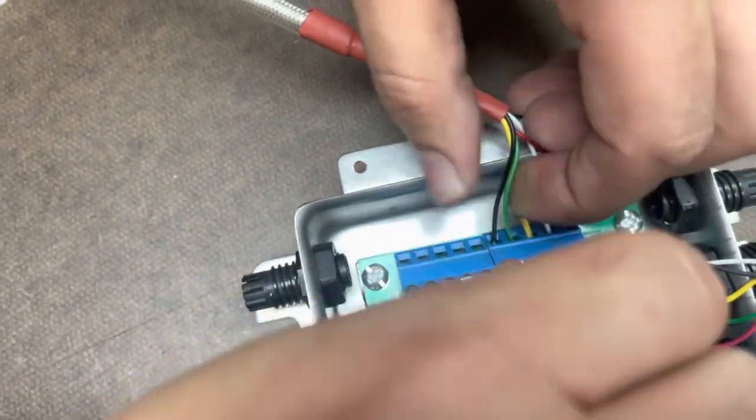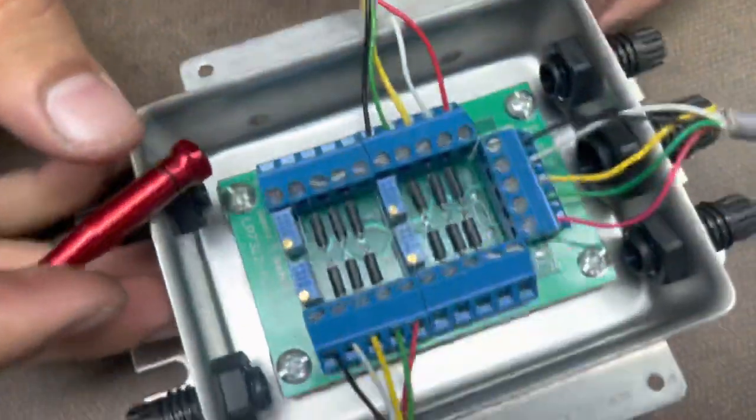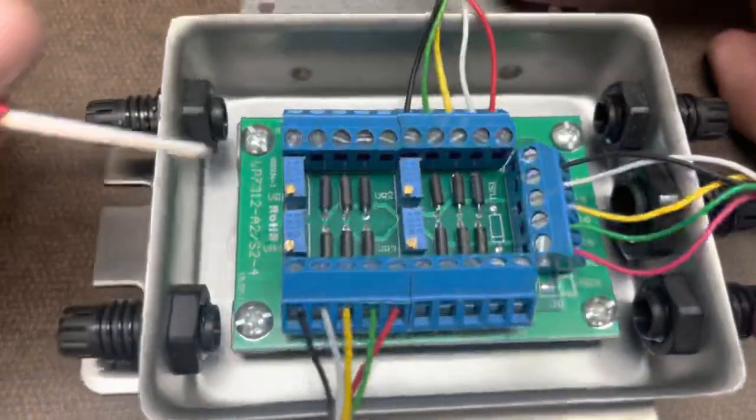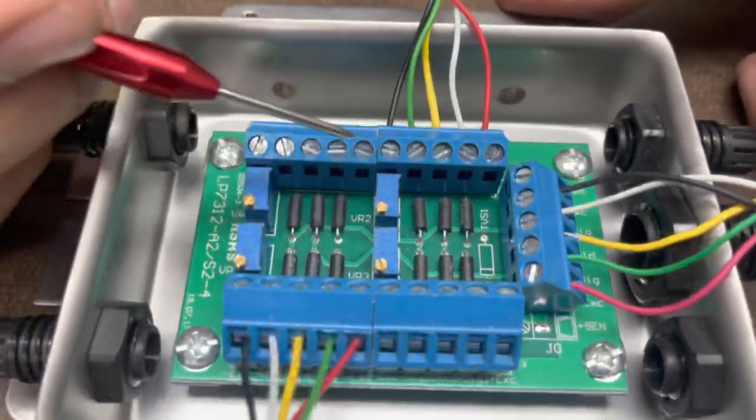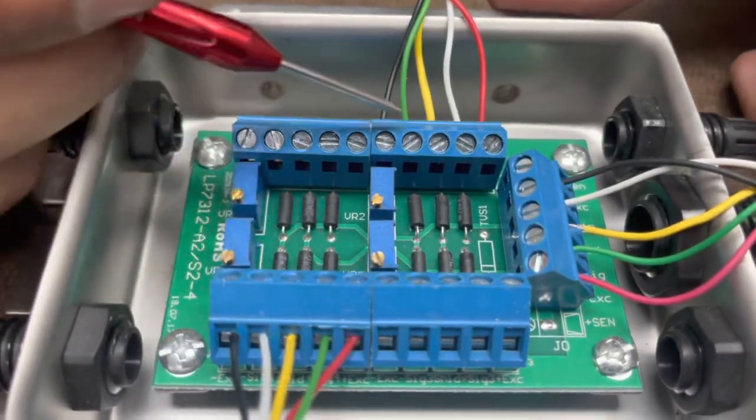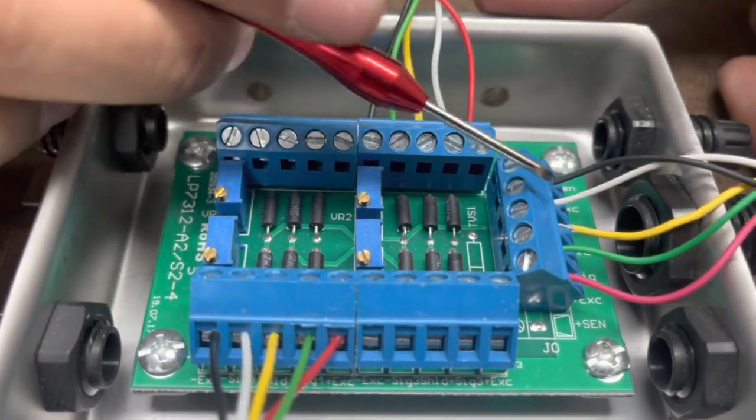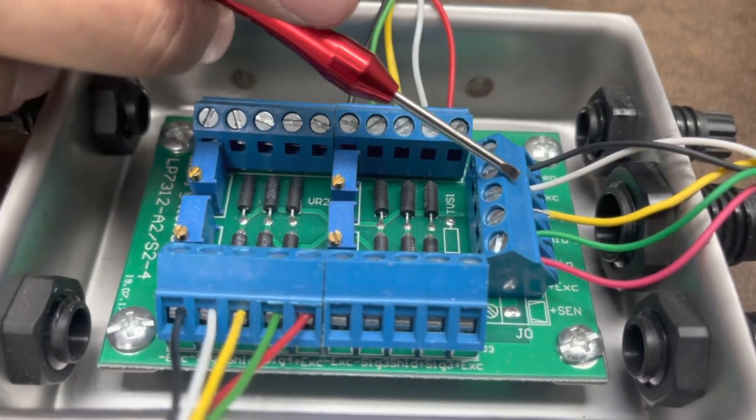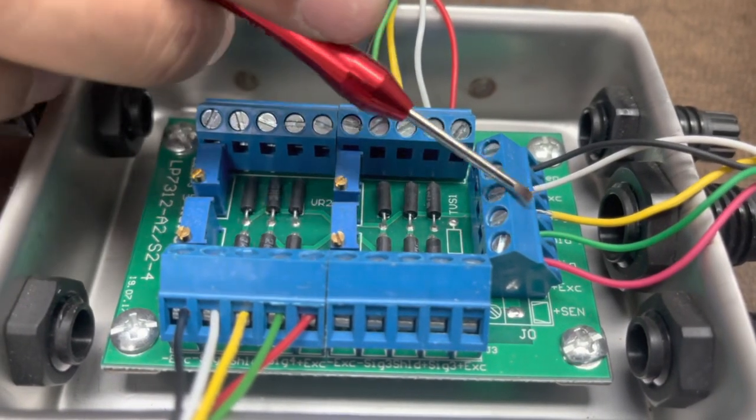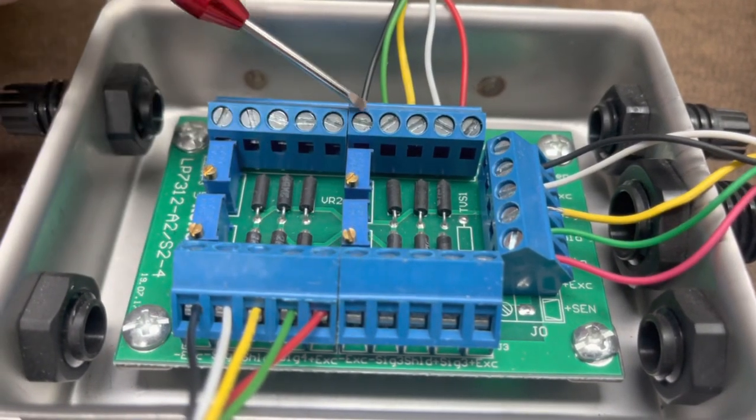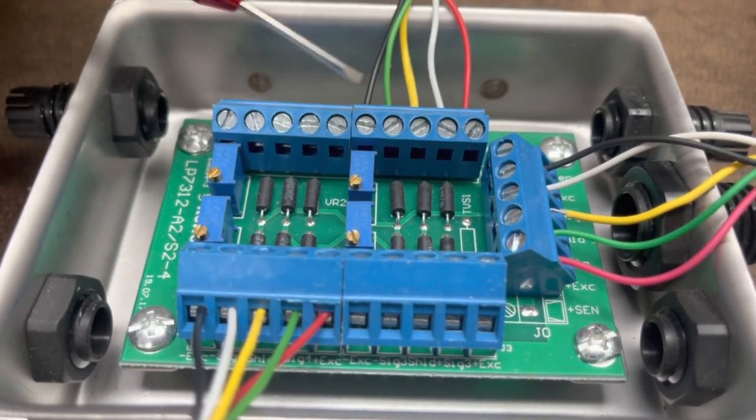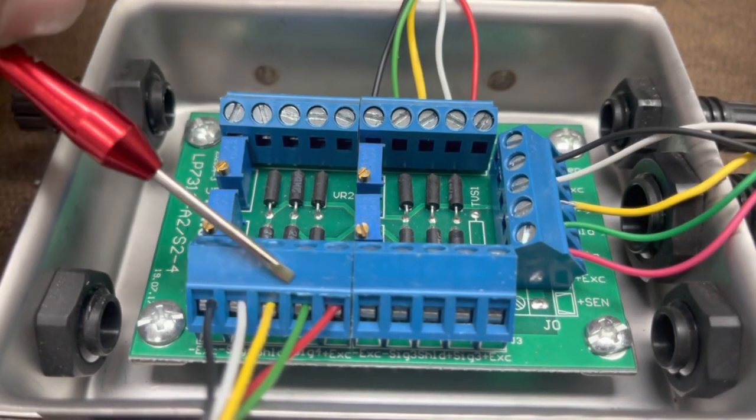So now we've switched the signal. Now, if you're going to switch signals, you have to do it for all four load cells, but leave the home run cable alone. This is the cable that goes to your indicator. We don't touch this. All we're doing is switching the direction of the load cell by switching the signals.